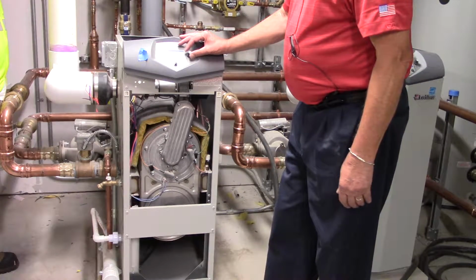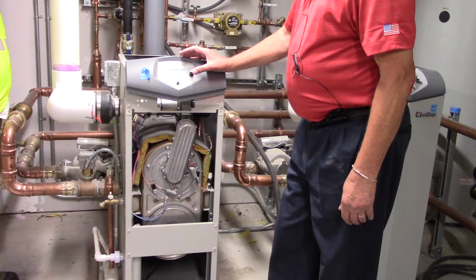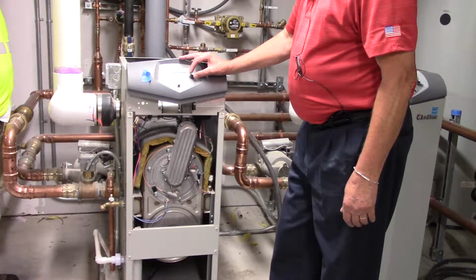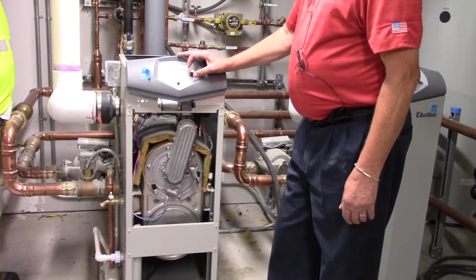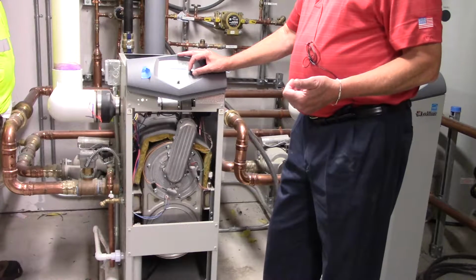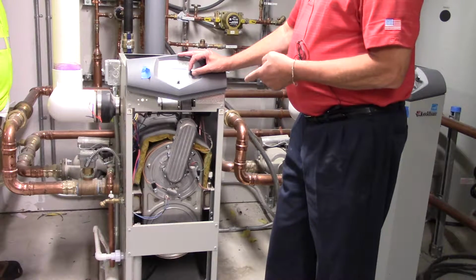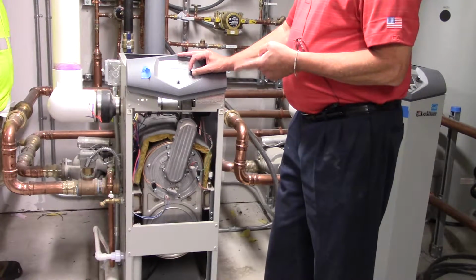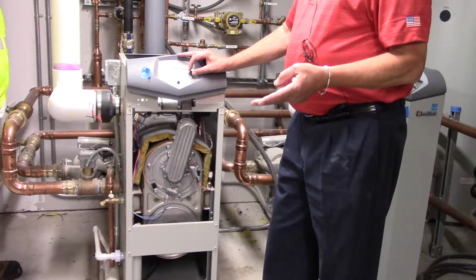It's also good information, because you go to screen 2, it's going to tell you what your flue temperature is. It's going to tell you if your domestic hot water pump is calling, if it's on. If you see that it's on this screen and that pump isn't running, then you've either blown a fuse or the pump's gone.